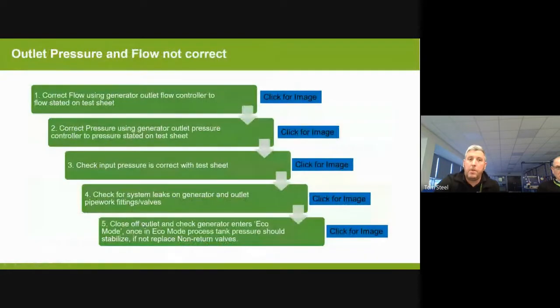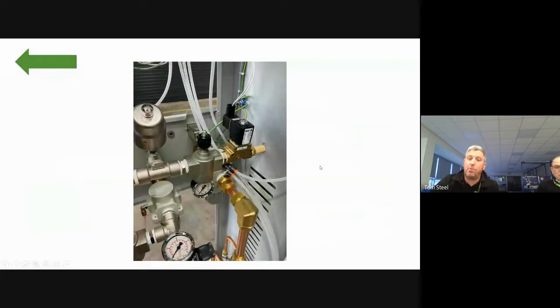Okay. So, if the output pressure and flow are not correct, you'll use the test sheet for that generator, okay? And the test sheet for that generator will tell you what to set this at, all right? So you'll have your output flow controller and your output pressure regulator. You set it as per the test sheet, the generator's specific test sheet. And the test sheet will be unique to that generator, but it's generally the same for anything of that specific size.